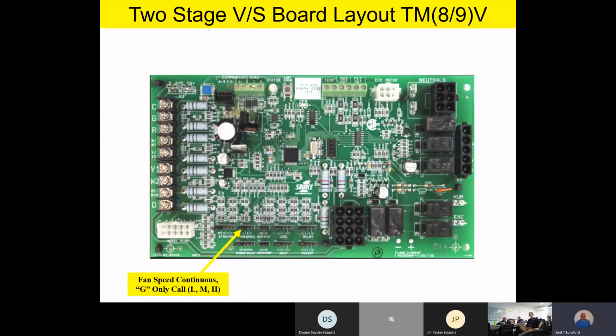How fast is the fan going to run? Well, that's what this jumper is all about. You have the ability to set that continuous fan airflow with a G only call to high, medium, and low. Now remember, this is a variable speed product, so this high, medium, low is going to be a percentage of high cooling airflow. So low is going to be 50%. Medium is going to be about 65 to 70% based on the model. And then high will be 100% cooling airflow.